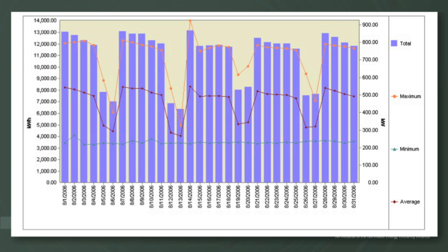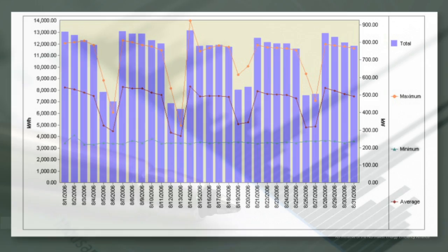So this is something you could go and look at and try to find out, looking at the individual days and possibly the weather pattern, and see what happened during that day. Now, all these questions that you come up with, the software isn't going to give you the answers. It's going to take a little bit of research into what happened during that day and finding out if somebody turned something extra on, maybe somebody came in on the weekend, maybe somebody overrides something for some maintenance. Those types of things are things you want to find out.